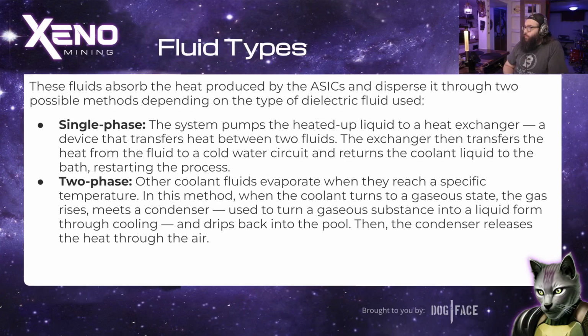Okay, so let's go into fluid types. Fluids absorb the heat produced by the ASICs and disperse it through two possible methods depending on the type of dielectric fluid used. We have single phase, where the system pumps the heated liquid to a heat exchanger, a device that transfers heat between two fluids. The exchanger then transfers the heat from the fluid to a cold water circuit and returns the coolant liquid to the bath, restarting the process. The bath is where the ASIC is submerged inside this dielectric coolant.